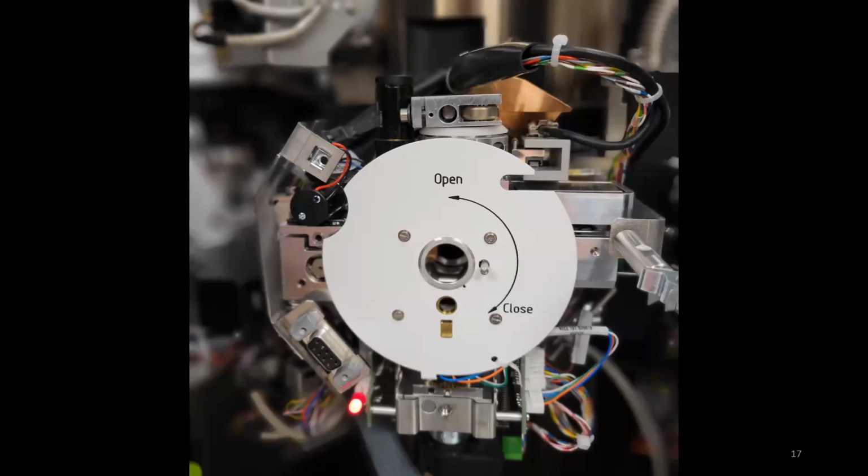So we can go 60 degrees in both the X and Y directions, or alpha and beta is what we'll call them. And it's really great. We can do a lot of stuff with that. It didn't used to be that you could do that because the pole pieces, which are part of the lenses, they used to extend down and they were really close. Over the years, they've gotten better and better. And so now you have more space in between there. And so it's easier to get these high angle tilts going on in your sample.